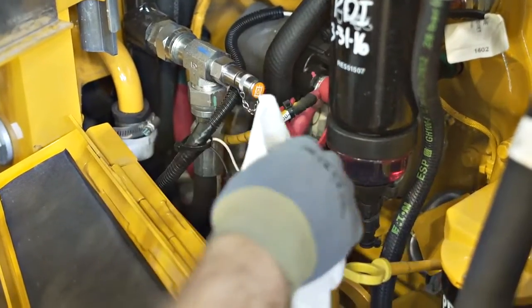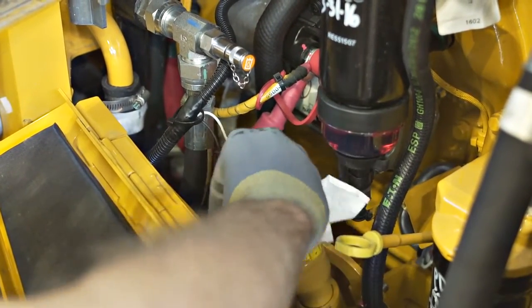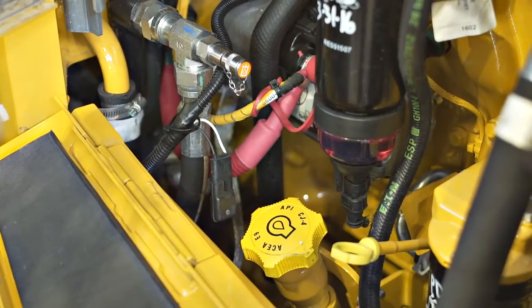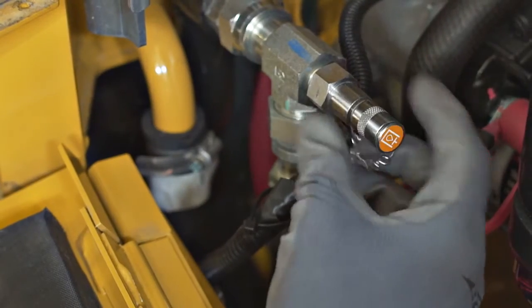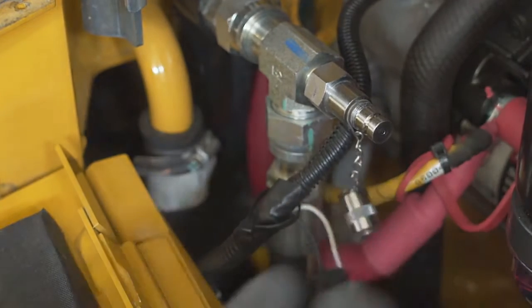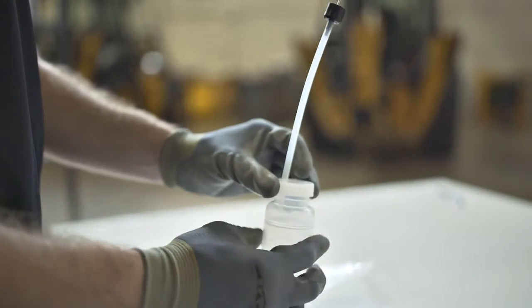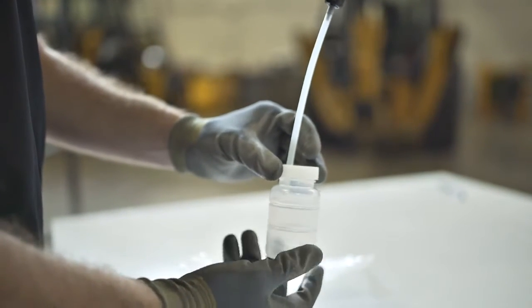Locate the sample valve on the unit and clean the area around the valve prior to removing the dust cap. This will reduce additional sample contamination. Once the area has been cleaned, remove the dust cap from the valve. Shop rags can generate and deposit fiber and lint. Ensure that the sample bottle is clean and free of any moisture before obtaining the sample.